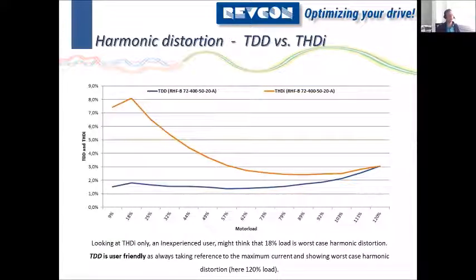So a non-experienced user looking at the THDI will look up here and say, oh, that's tricky and that's too high and I'm worried about the current up here. And they don't need to be worried because we still have 3% or 8% harmonic distortion, which is higher than up here, but still the input current is only 18% in this example, or the motor load is only 18%. So we are speaking about 8% of 18%. And here we are speaking about 3% of 120%. So you always need to check what is the biggest value. So looking at the TDD, you already have that included. So you can automatically see, okay, this is the worst case, 120%. That's what I need to care about.